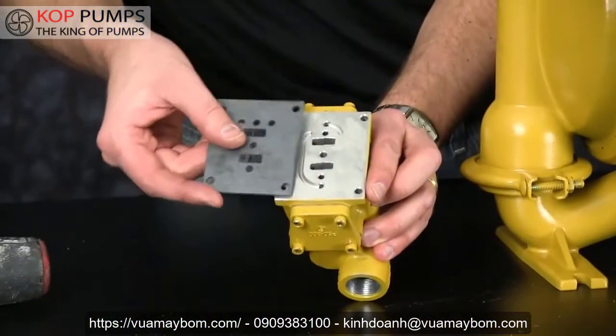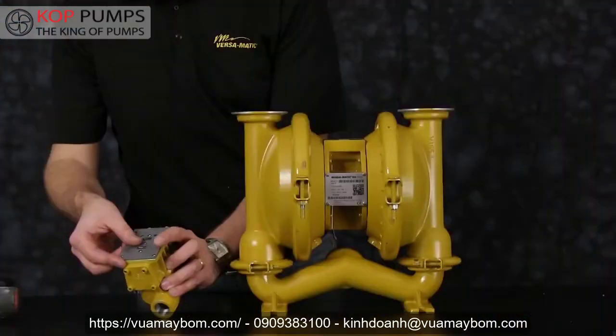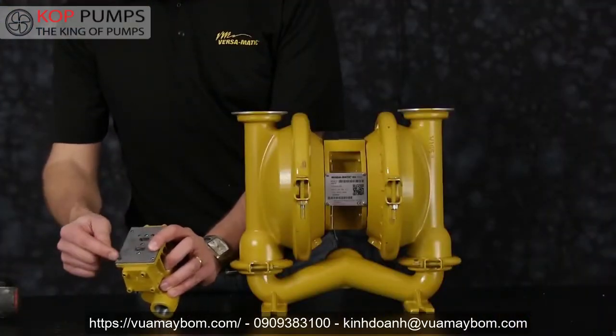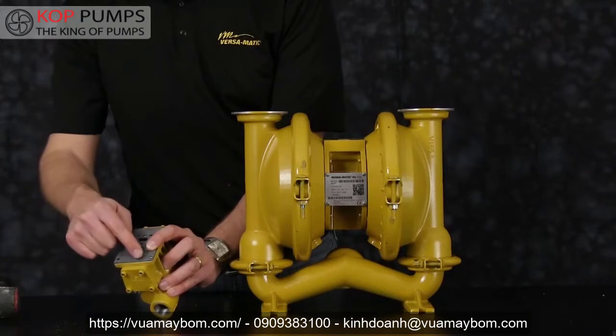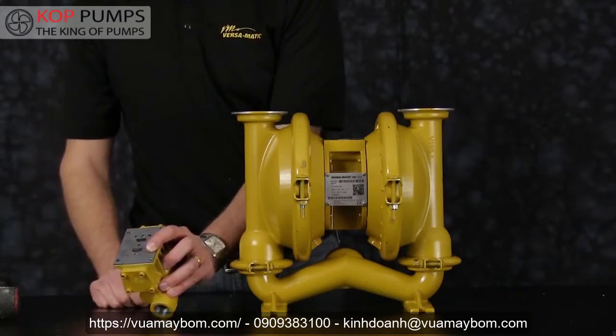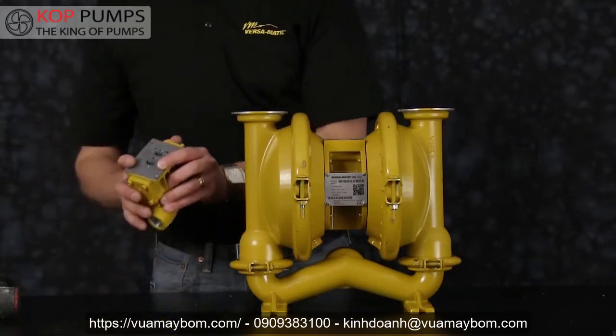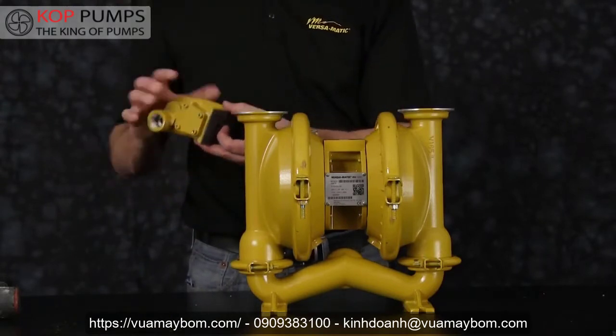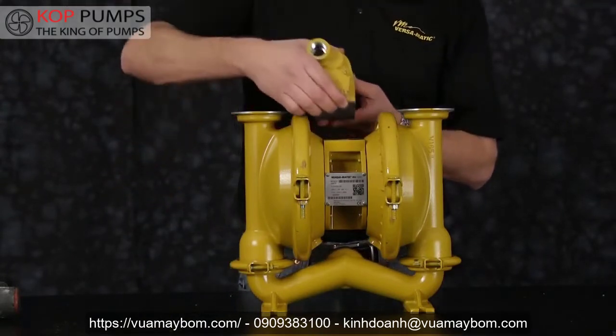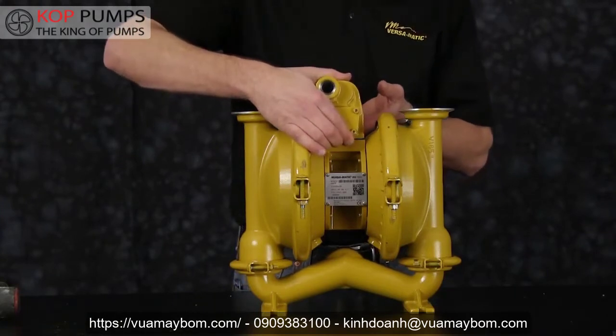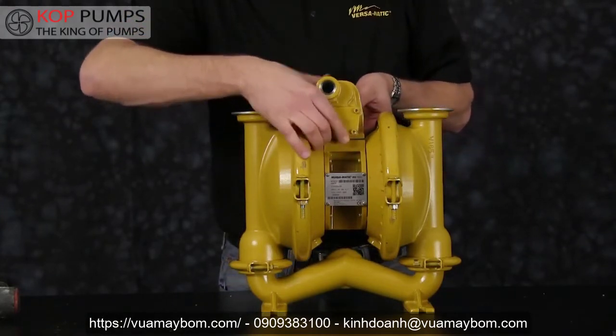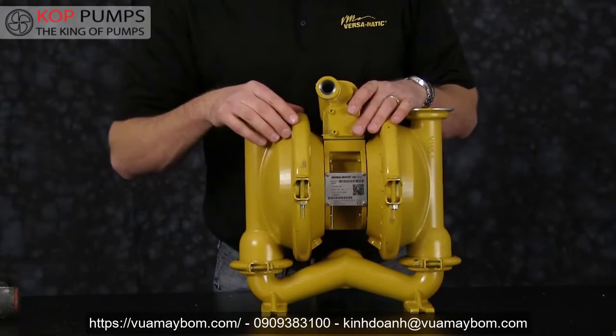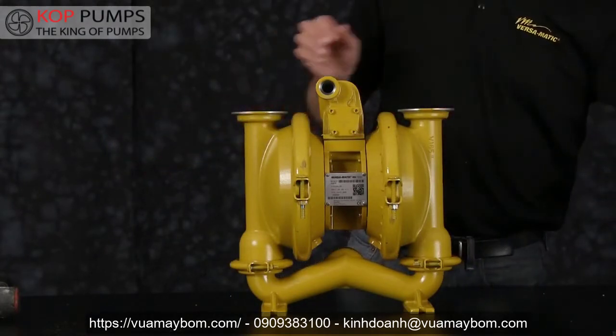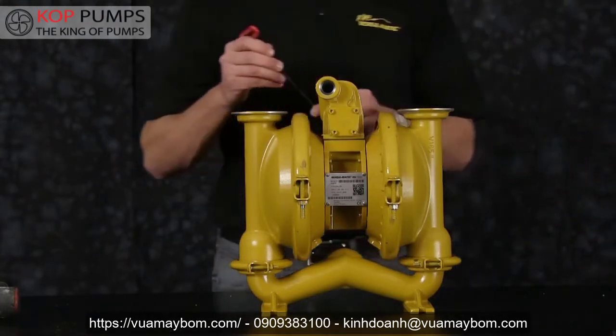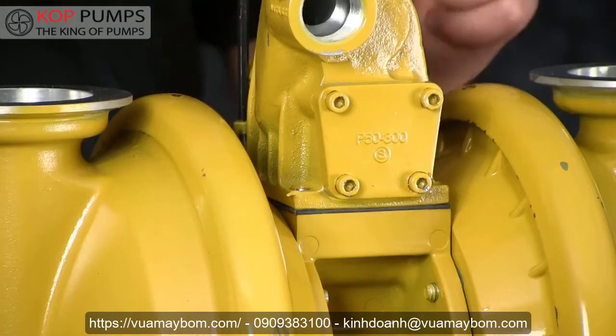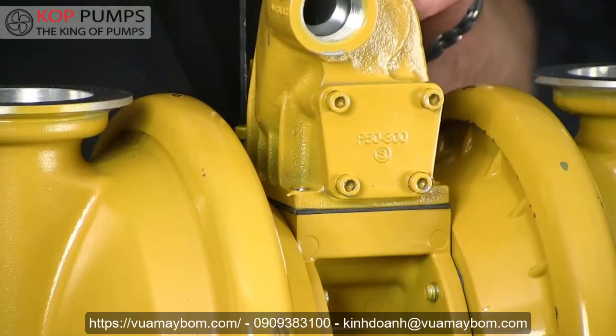Now ready to install our main air valve assembly to the center block of the pump. Be sure to align all the bolt holes of the main air valve gasket with the main air valve body and the pilot porting holes. Note the orientation of the main air valve assembly in relation to the center section of the pump. Tighten the main air valve assembly to the center block of the pump.